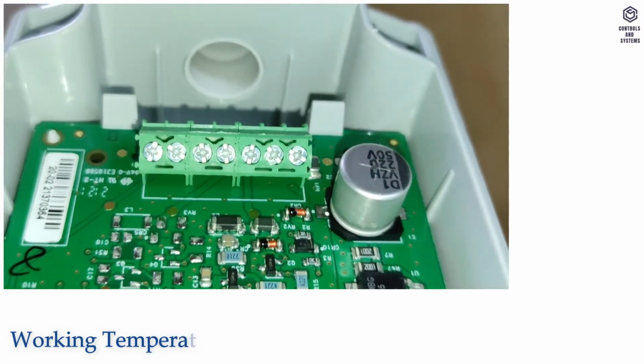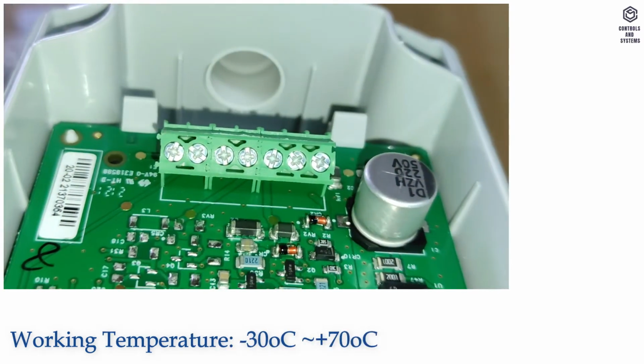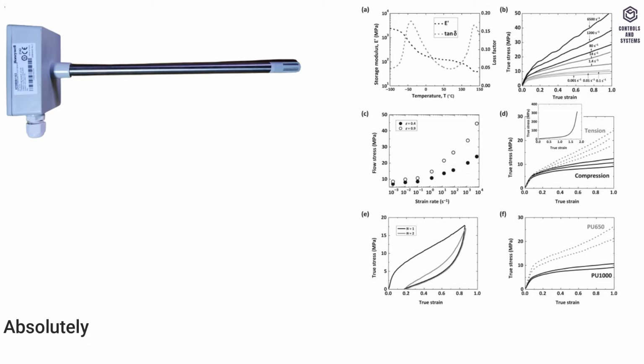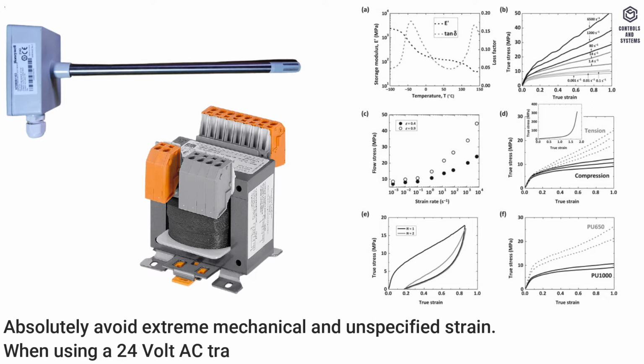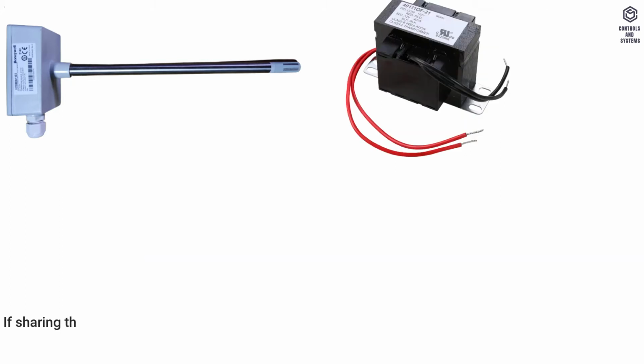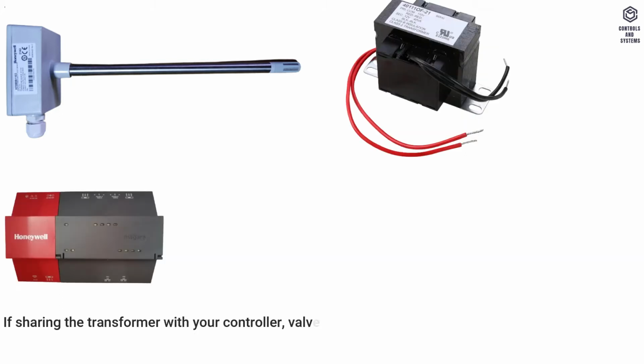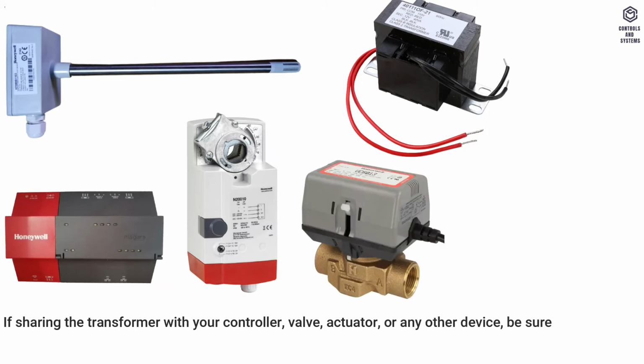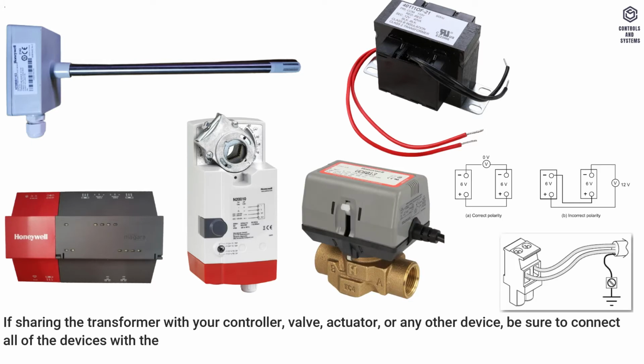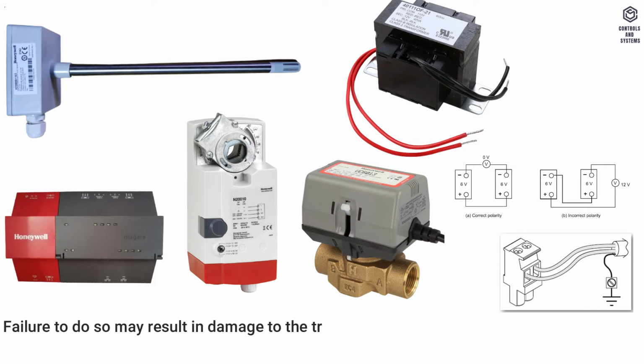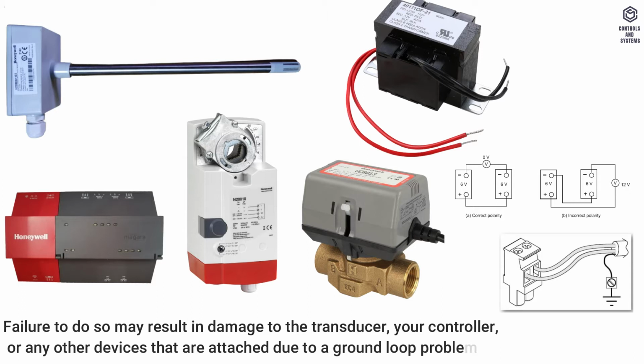Working temperature is minus 30°C to plus 70°C. Attention! Absolutely avoid extreme mechanical and unspecified strain. When using a 24-volt AC transformer, use an isolated transformer, class 2, if sharing the transformer with your controller, valve, actuator, or any other device. Be sure to connect all of the devices with the proper polarity, since most controllers are earth grounded. Failure to do so may result in damage to the transducer, your controller, or any other devices that are attached, due to a ground loop problem.